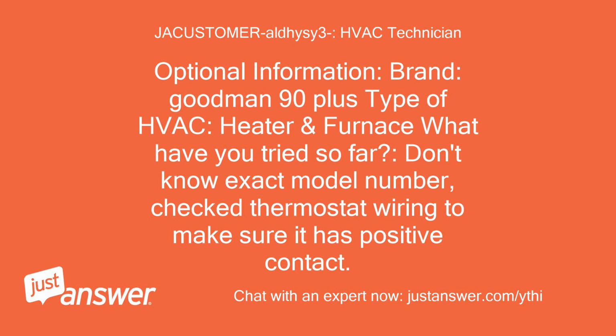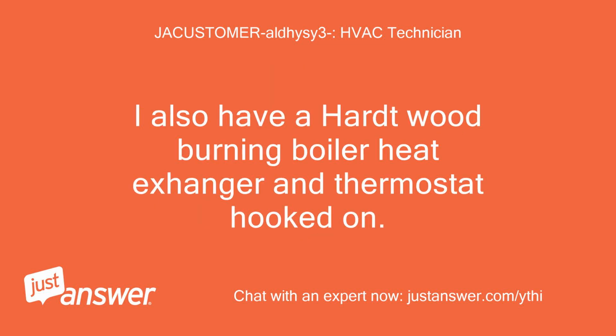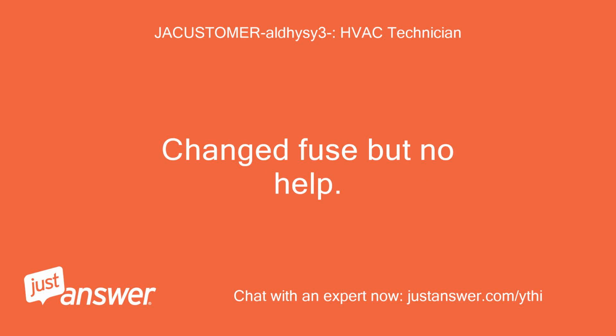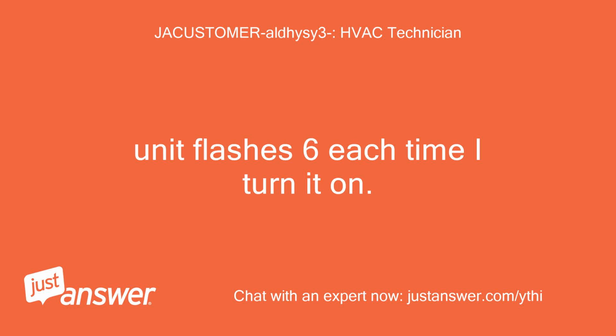What have you tried so far? Don't know the exact model number. Check the thermostat wiring to make sure it has positive contact. I also have a Hardt wood burning boiler heat exchanger and thermostat hooked on. Cannot get either one to work, as the blower kicks on and stays on. Changed fuse but no help. Unit flashes 6 each time I turn it on.